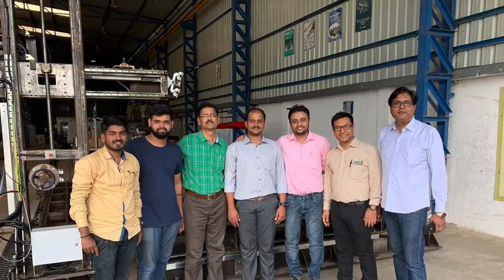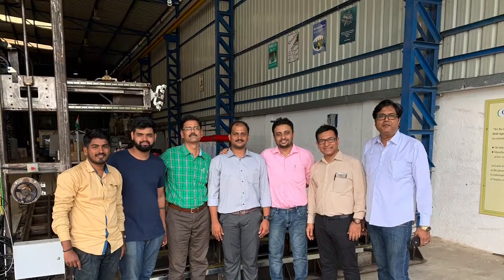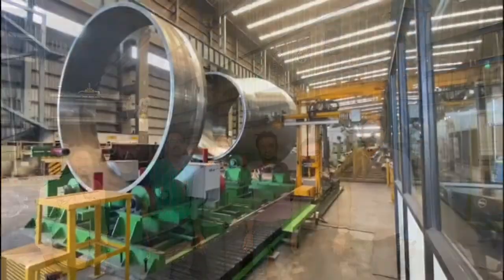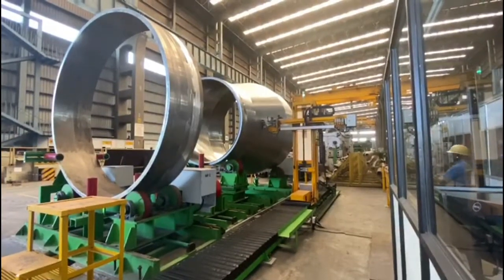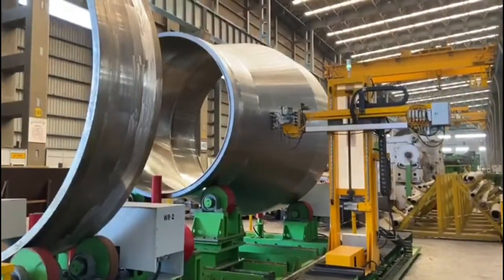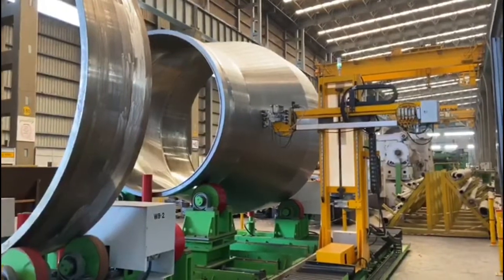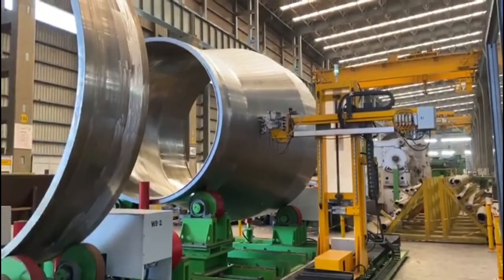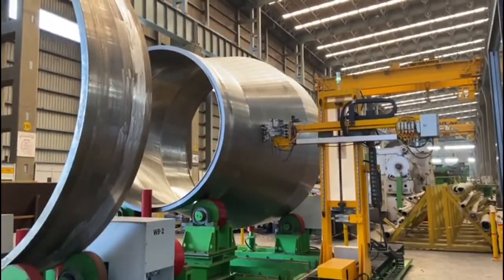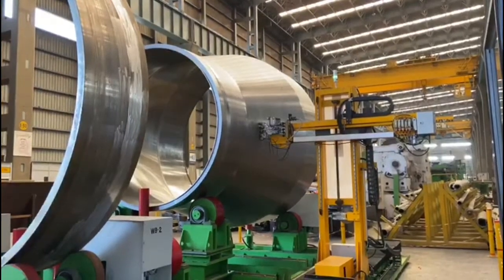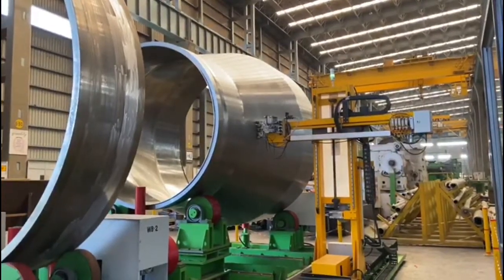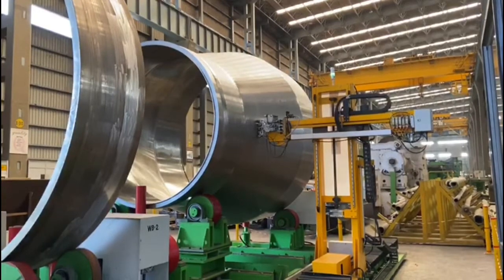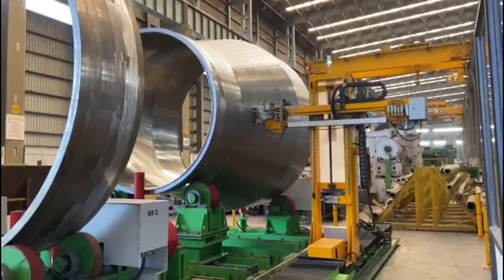Gantry and rotator system for automated ultrasonic testing of shells. This system is made for ultrasonic testing of big shells weighing up to 40 metric tons. It consists of rotators of two types, one for testing the main shell and another for a test rig used for UT probe calibration. For probe movement, there is a gantry.